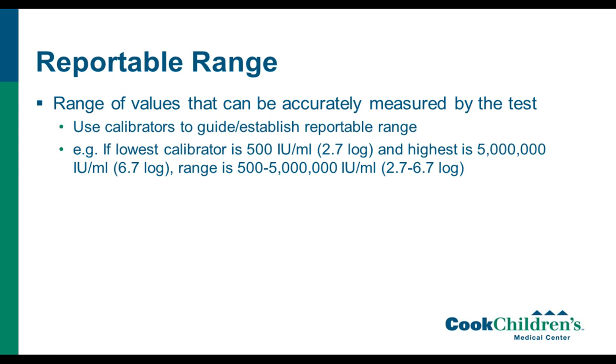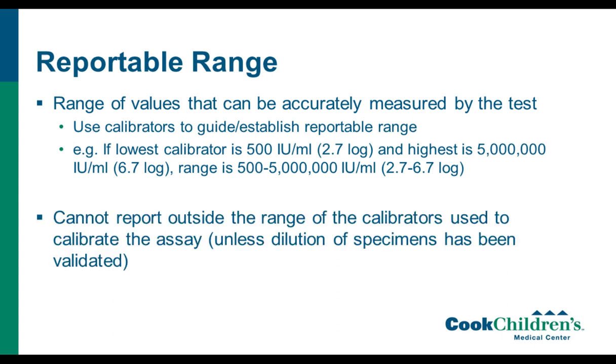So one of the panels that we use for our calibrator panels, the lowest calibrator is 500 IUs per mil, or 2.7 logs, and the highest is 5 million. So our range for that assay is 500 to 5 million. We found that it performs accurately along that specific range. And you have to have it documented somewhere, either in your validation or verification, in your standard operating procedure, or some people also will put the range on their report that goes out into the electronic medical record.